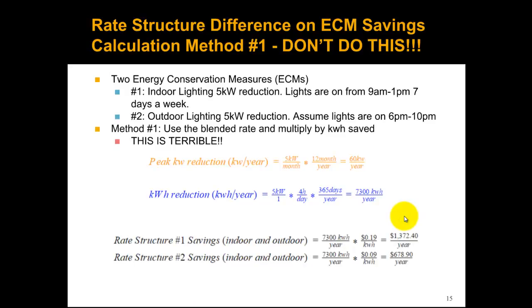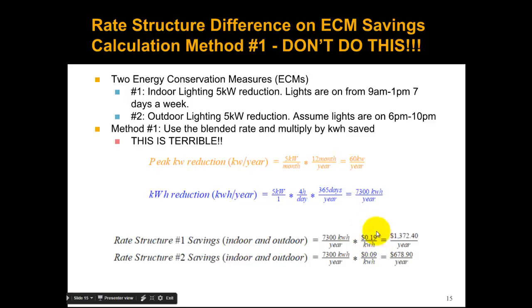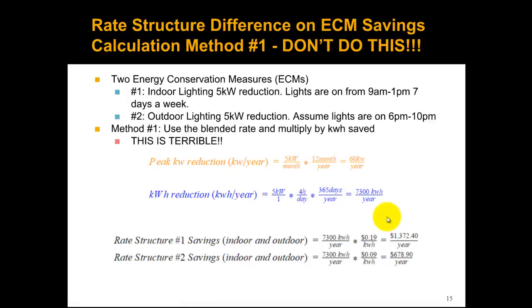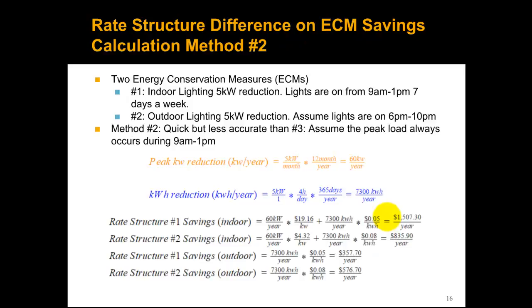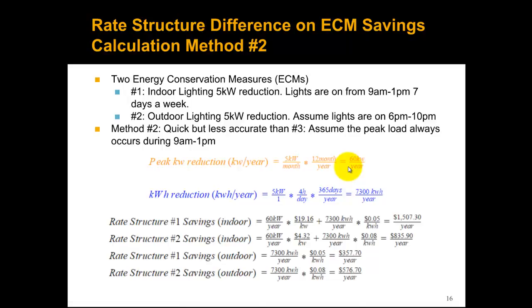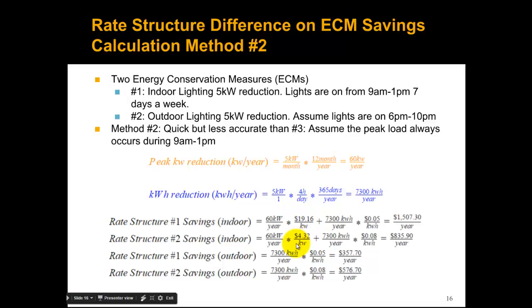Now let's look at method number one using the blended rate for energy savings. With the blended rate we don't even consider peak kilowatts — we just multiply by the blended rate: 19 cents per kilowatt hour for rate structure number one, and about 9 cents per kilowatt hour for rate structure number two. For method two, assuming the full 60 kilowatts per year with indoor lighting, those indoor calculations include the peak charges multiplied by the peak charge rate for that structure, and the outdoor ones don't include the 60 kilowatts per year. You can go ahead and check my math closely if you want.